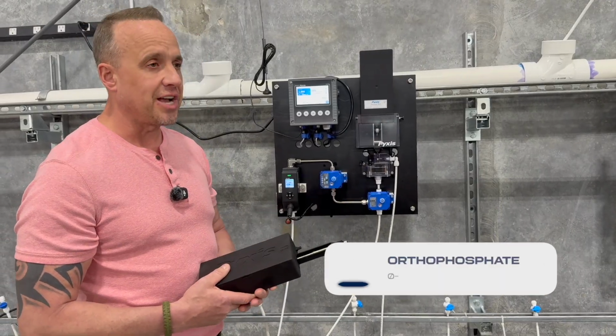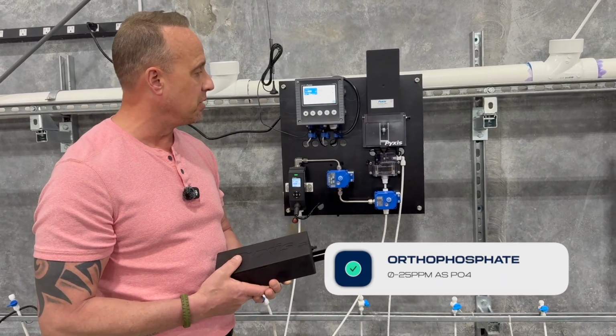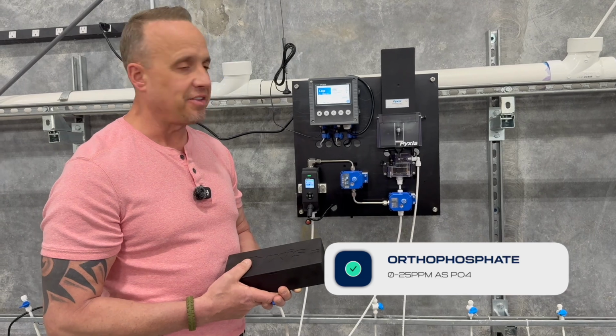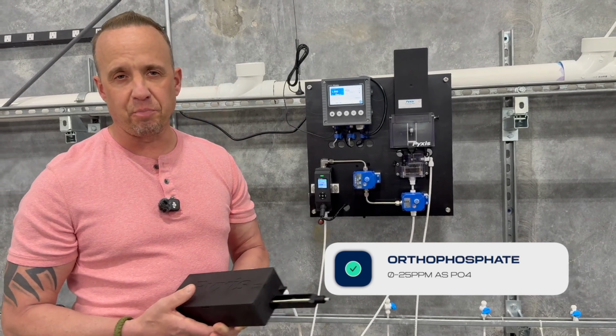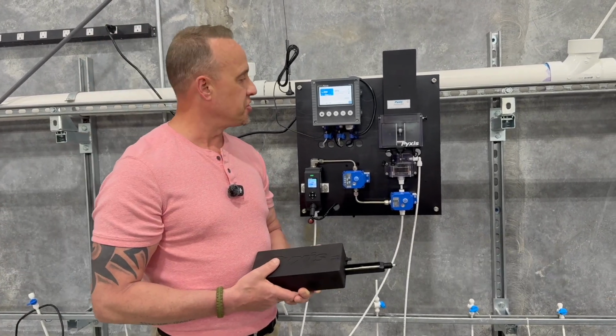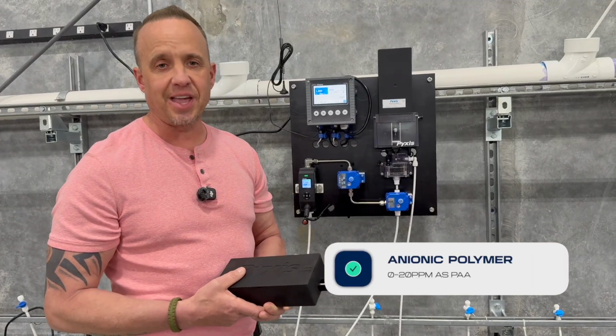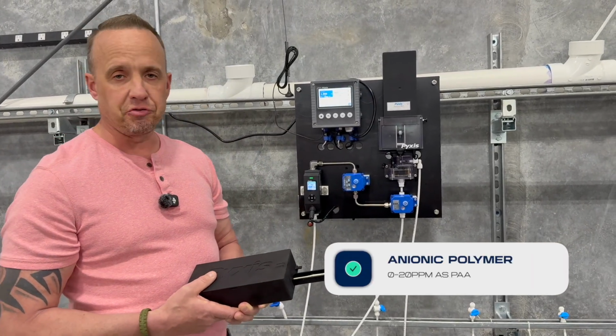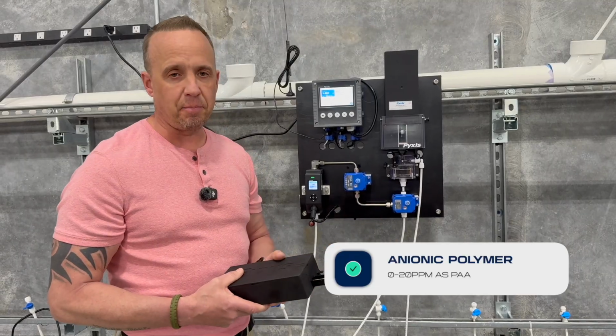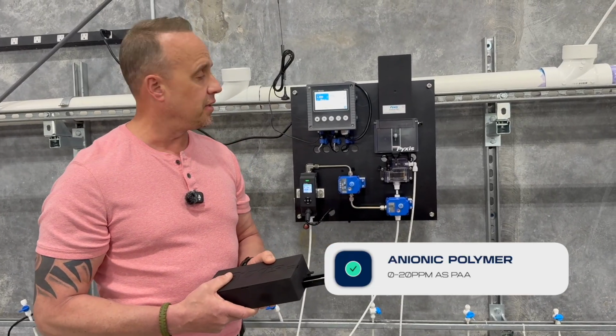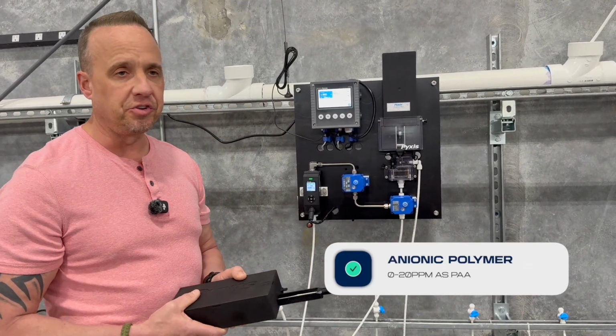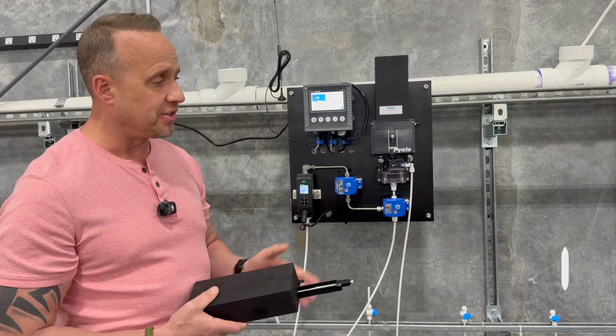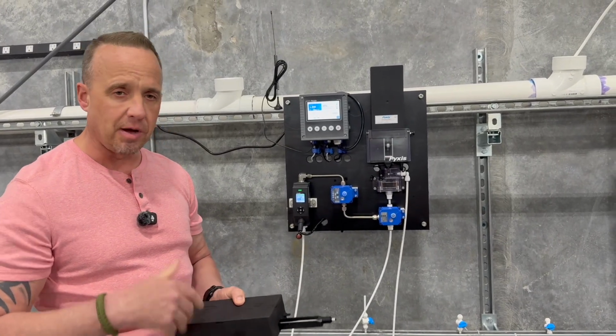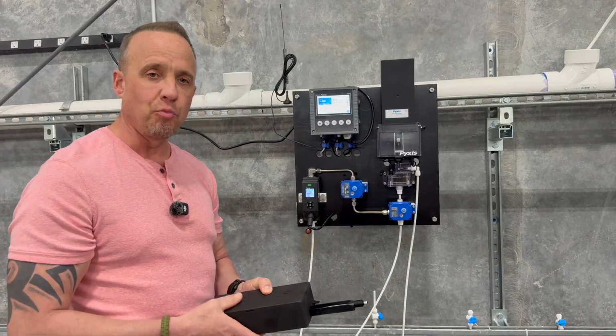The fourth version is actually for orthophosphate. We'll use a molybdate method with the capacity of measuring between 0 and 25 parts per million. And the fifth version is anionic polymer measured as AA amps. That would be used in conventional cooling water chemistry that's using anionic polymer or AA amps chemistry in their application, and they want to know polymer residuals. A rather broad offering. Again, this is generation 1. Generation 2 will be coming in a few months to offer even more tests and more capacity.